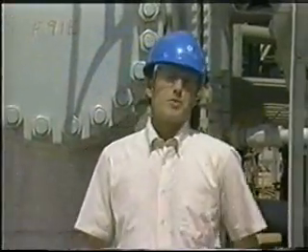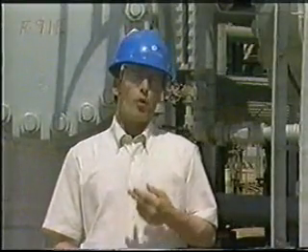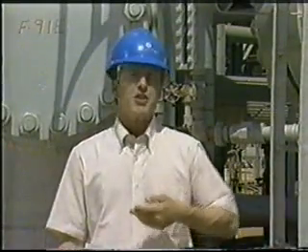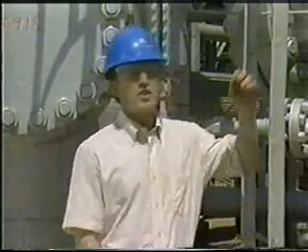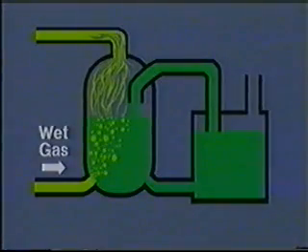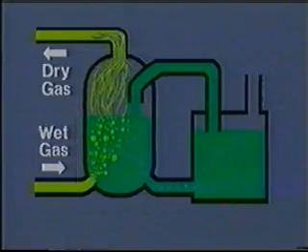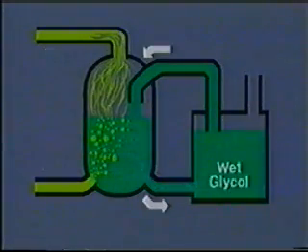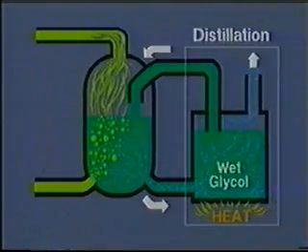There are two basic purposes to a glycol dehydration facility. The primary purpose is to dry natural gas before putting it in a pipeline. The secondary purpose is to remove the water from the glycol so that it can be used over and over again. The process is actually quite simple: the wet gas has water removed from it as glycol soaks up the water, leaving dry gas. The wet glycol then goes through distillation where the water is removed by boiling, and the glycol is recycled to function again in the dehydration of gas.